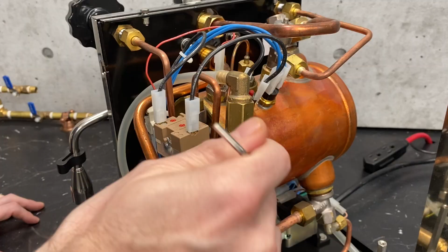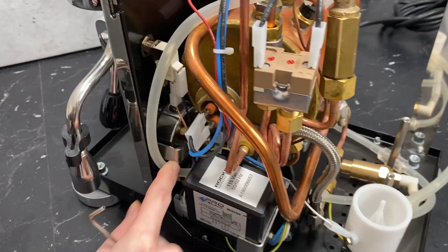So off the top end here, you got this other line that comes off. This almost looks like an expansion valve. This is actually your safety valve. So basically, if your boiler were to overheat, go over the set pressure on that, it will blow out that pressure through that little tube there, and this little tube, if you can see, straight down in there goes to another little boot. There's a white boot there that it connects to, and that would come out the front of your machine there. Right, that little button in the center. Okay.